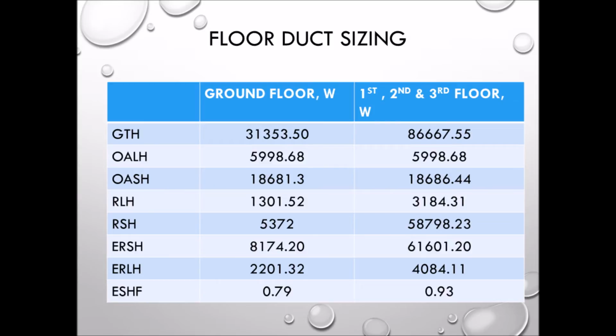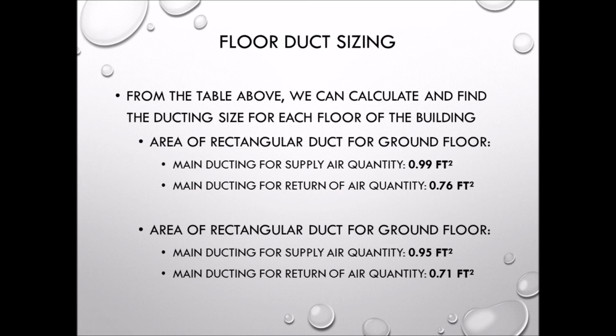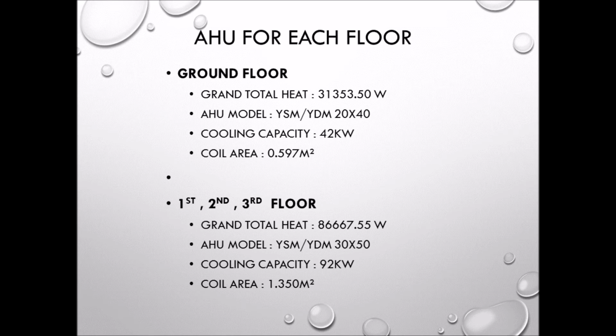So for the floor duct sizing, this is the summary table we made for the ground floor and the other floors, first, second and third floor. So we need to know the floor duct sizing that is suitable for our office to get the desired airflows. From the table above, we can calculate and find the ducting size for each floor of the building. So we can know the area of the rectangular duct for the ground floor and the first, second and third floor. So this is the calculated air handling unit for each floor.